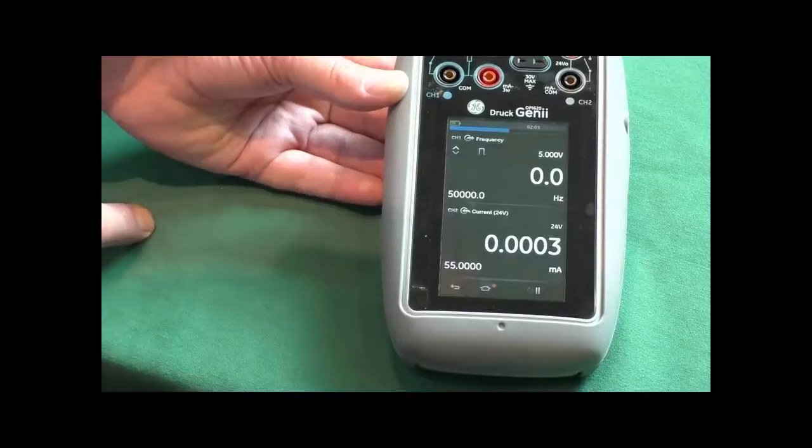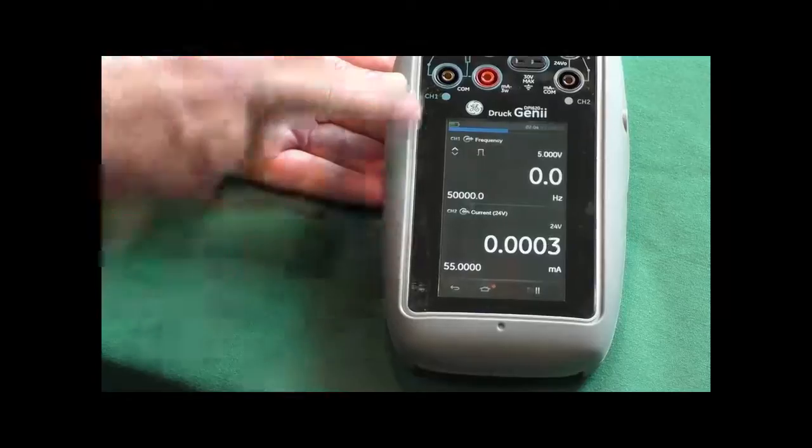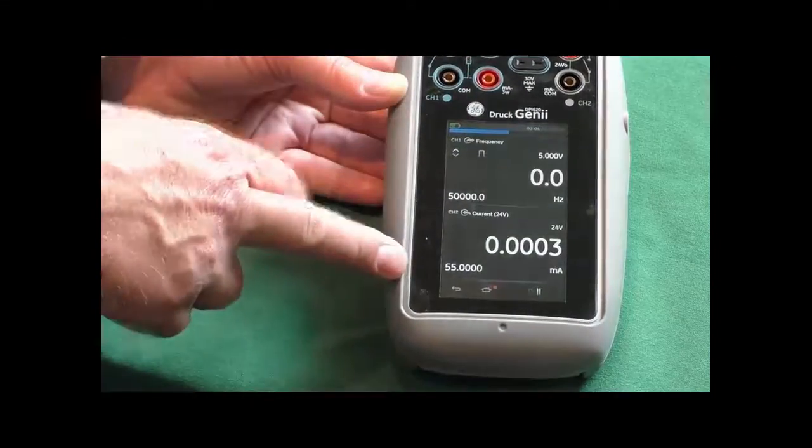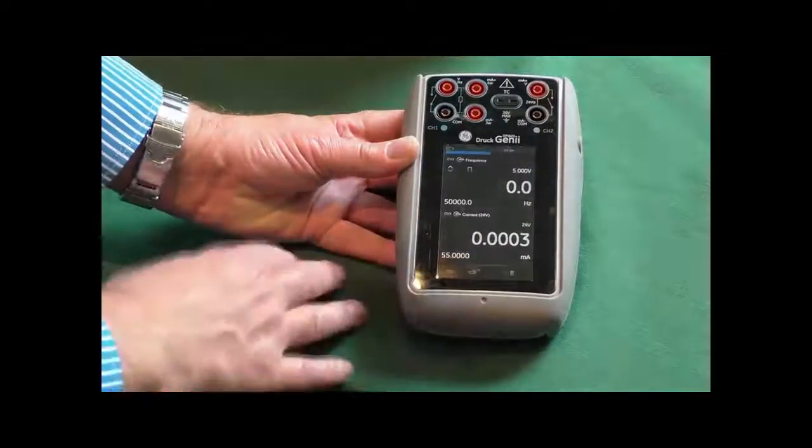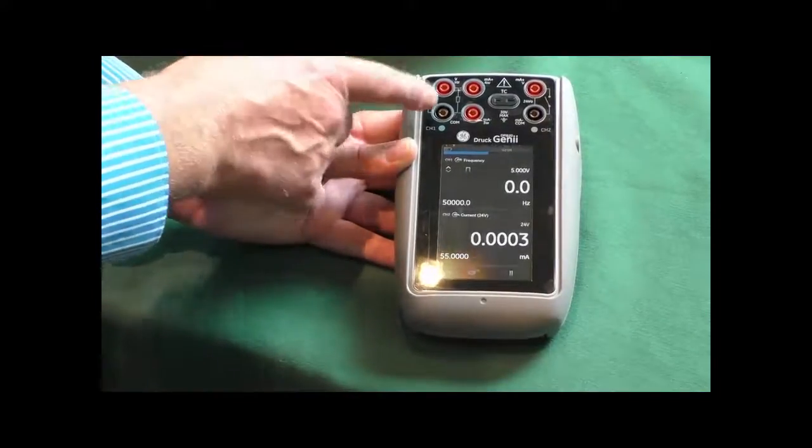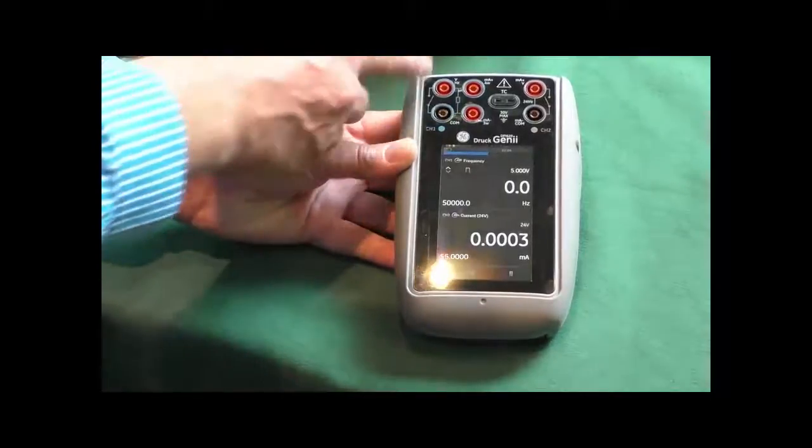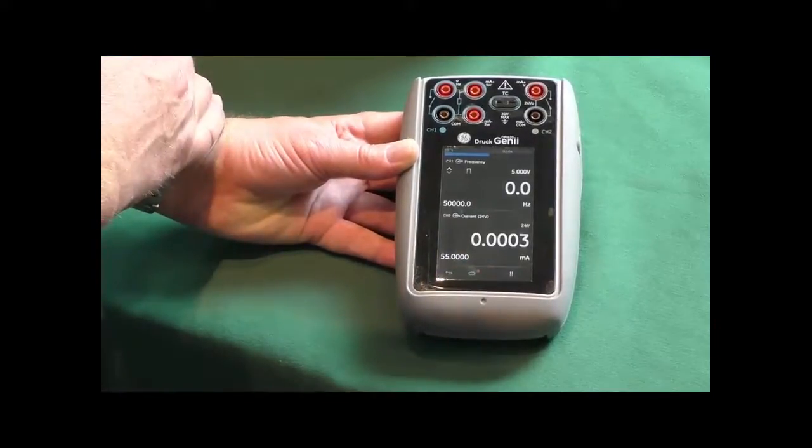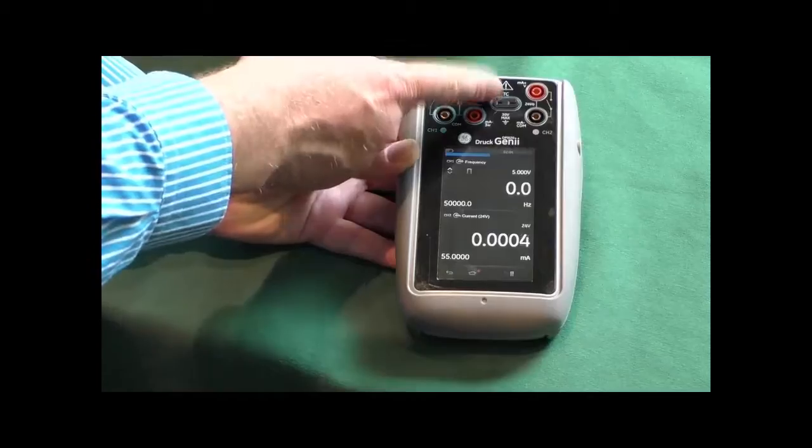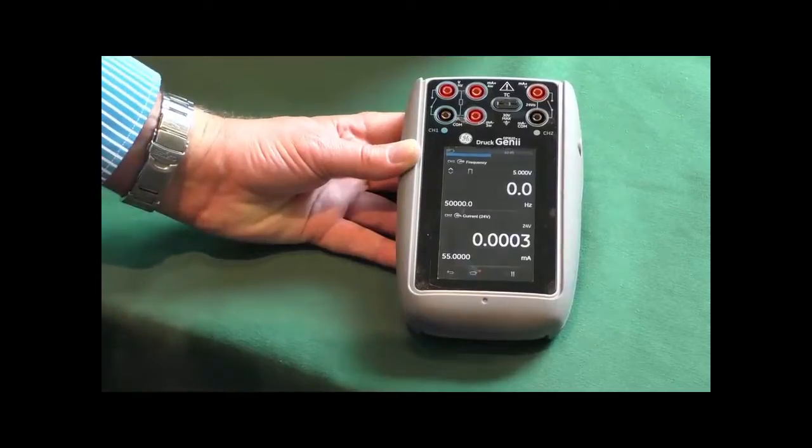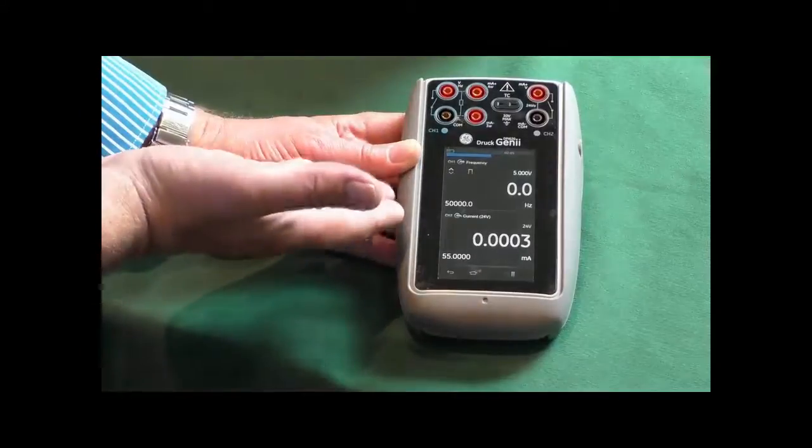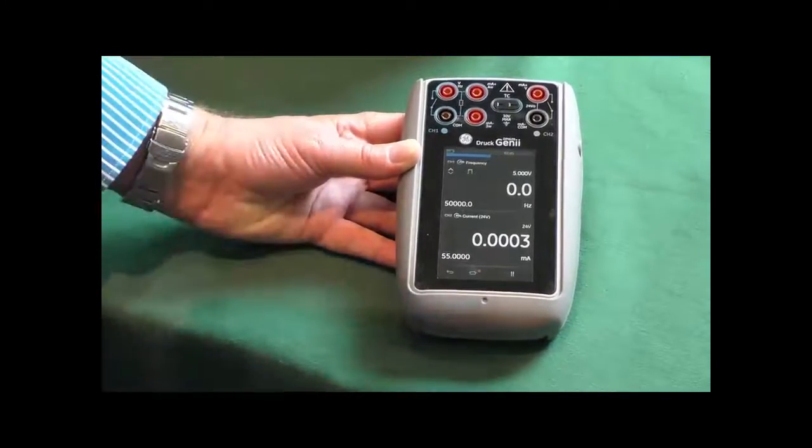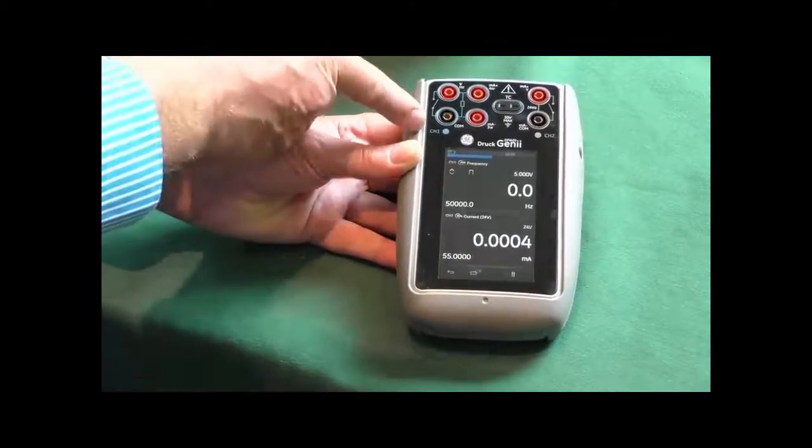So this is calibrator mode. Now we can set a number of channels on here. At the moment there are two channels that have been set up. We've got channel 1 and channel 2, and on the screen we're displaying those two channels now. So on channel 1, as you can see, we've got some graphics on there indicating what we can do. We can measure or source or measure a full four-wire RTD, up to a four-wire RTD, and it will test all the compensation lines on there. We have our thermocouple connection here, and over on this side we have a milliamp and a 24-volt power supply. So we're working with the transmitter, so what I want to do is power that transmitter from this device. So I'm going to provide 24 volts to do that, and as this transmitter's input is an RTD, I want to simulate an RTD on channel 1.